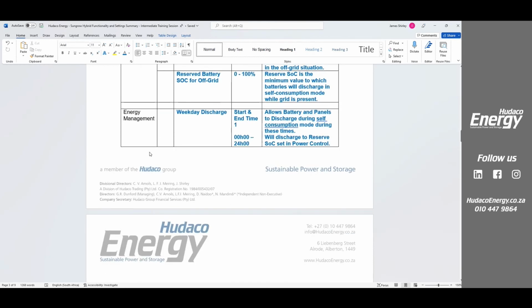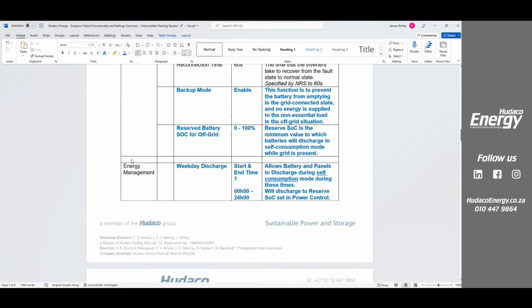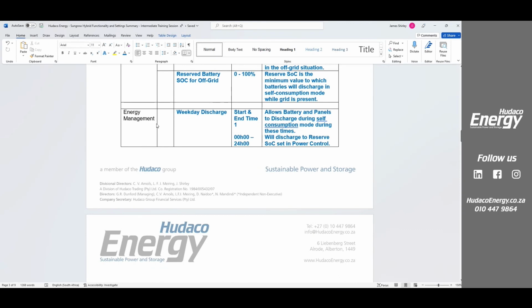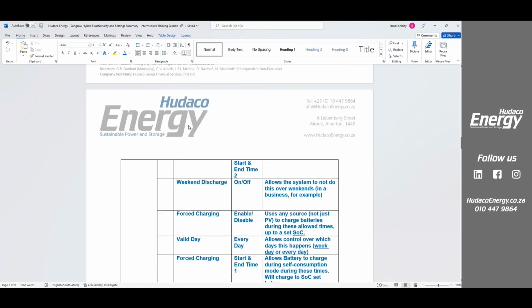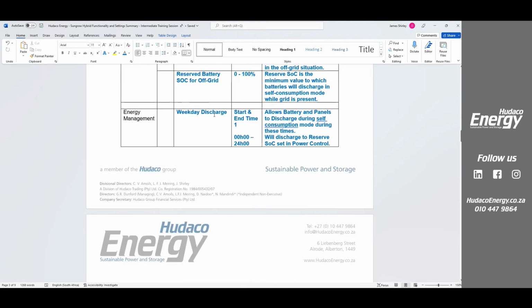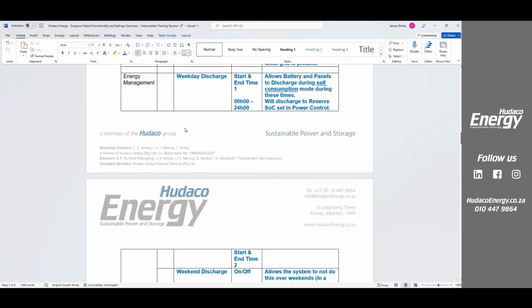The next option or the next category is instead of power control, it's energy management. And this allows us here to do weekday discharge times. So in other words, this allows the batteries to discharge during self-consumption mode. For South Africa, on residential, we do not have time of use tariff. So in other words, it pays us to use our energy first from the batteries.